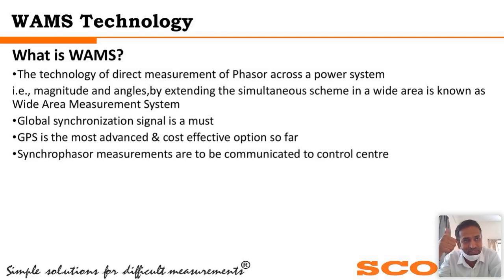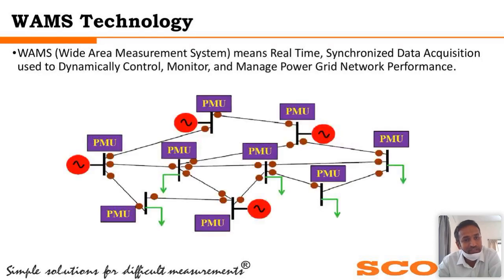One is the phasor measurement unit. The second is the GPS signal. The third is that, just as you have a SCADA center, you should have one PDC, the phasor data concentrator, where all this phasor data is collected for future analysis. This is what WAMS technology is coming up with. Under this WAMS technology, we are mainly using the PMU.